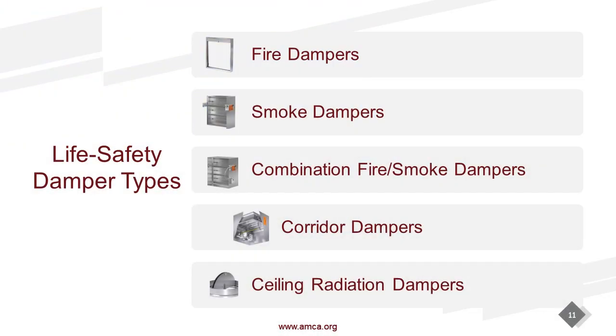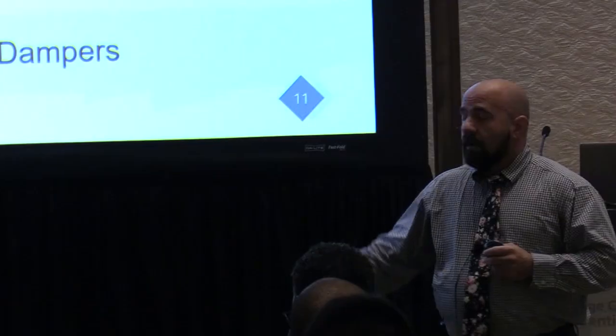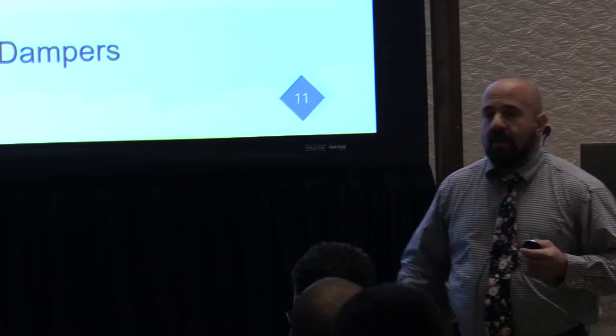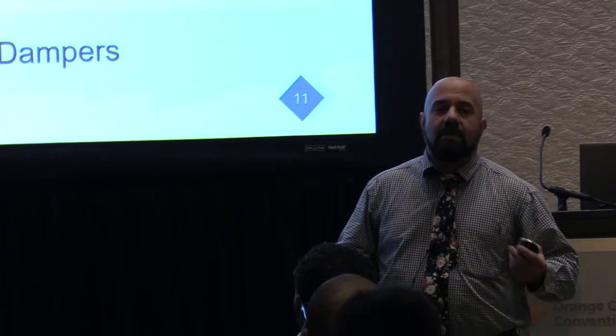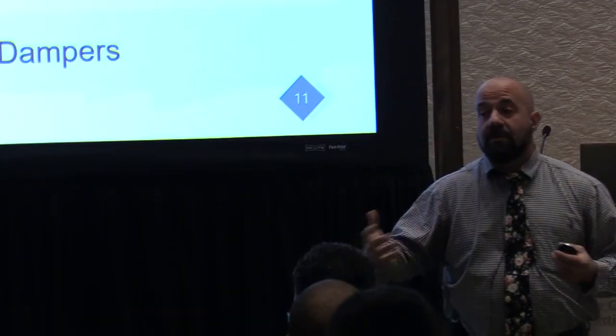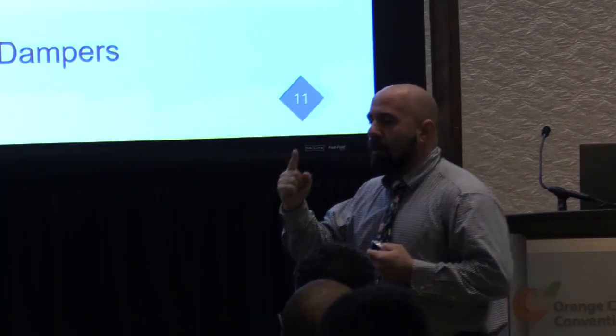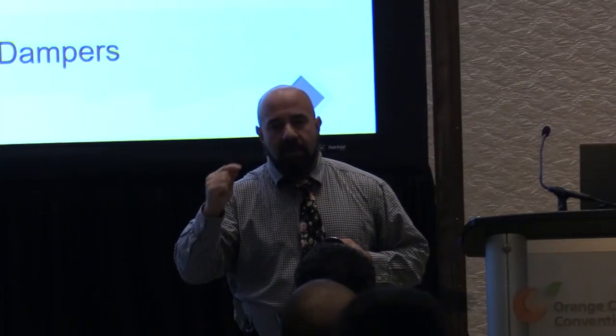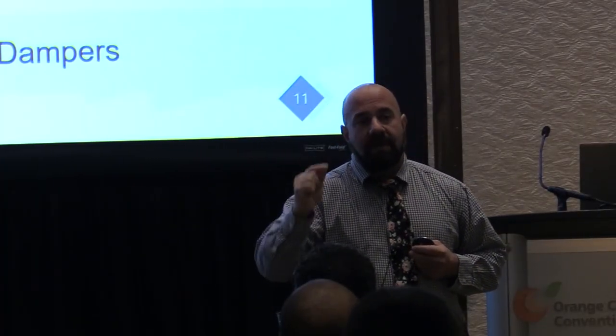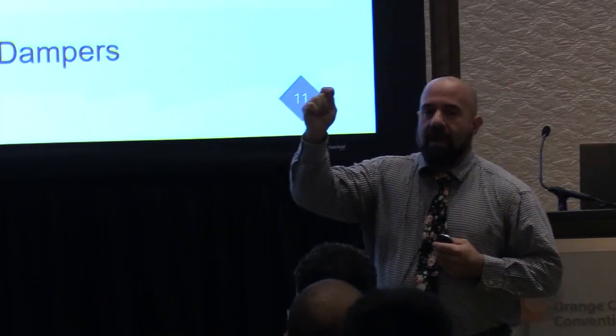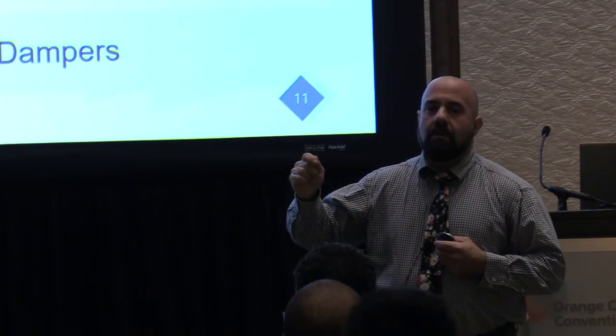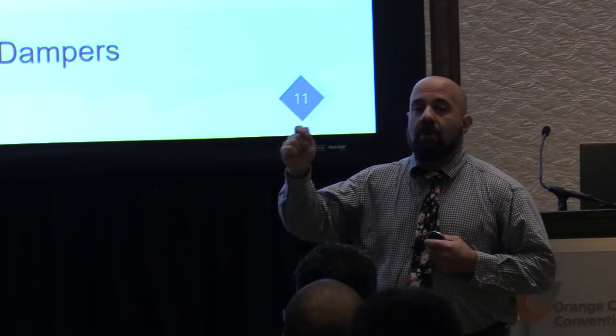All right, so what are my types of dampers? They're up there. We have fire dampers. We have smoke dampers. We have combination fire smoke dampers, and we also have ceiling radiation dampers. You notice I skipped corridor dampers. They are just a subset of combination fire smoke dampers. They undergo some additional testing. They get a 1-hour corridor rating for use in egress corridors. California Building Code requires that. It's in the International Building Code. It's not part of the National Building Code of Canada, so corridors are treated a little differently.